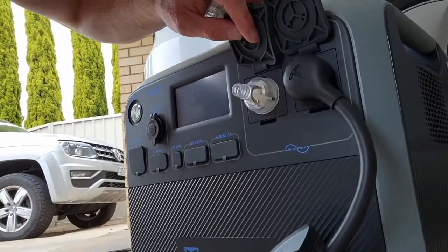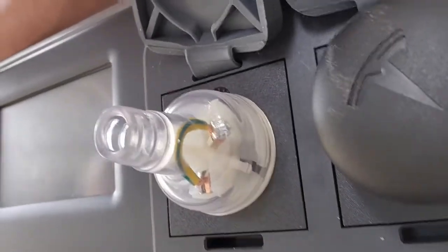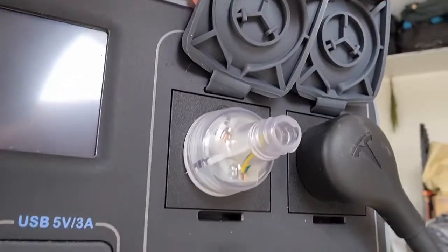We just got the same fault error saying inadequate ground or no grounding. So what I ended up doing — the forbidden approach — I took a bit of a risk because I'm not an electrician, and did the neutral-to-ground: I wired the neutral to the ground. You can see it's a clear little connector. Obviously the active is not at all grounded.